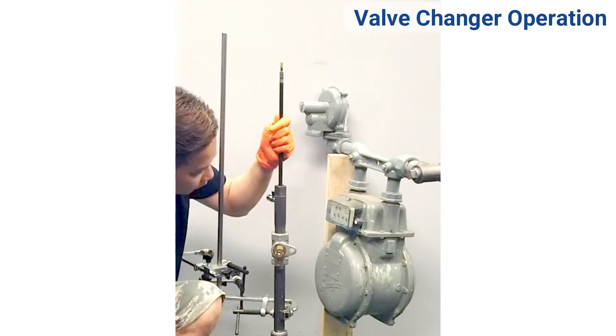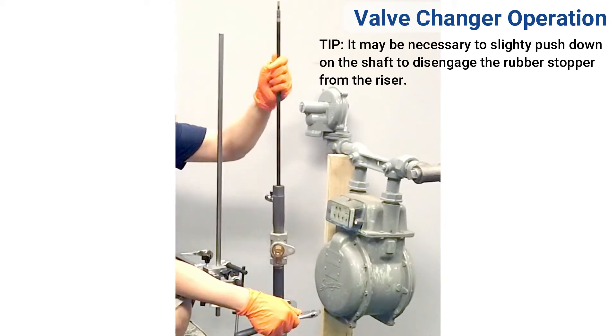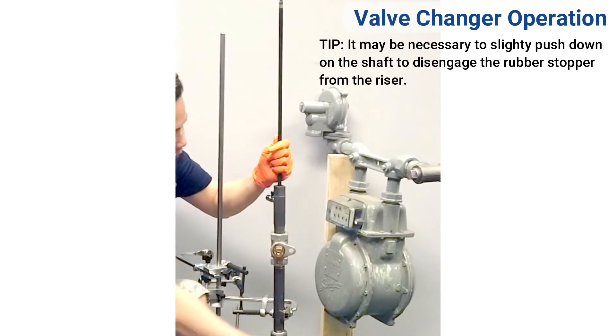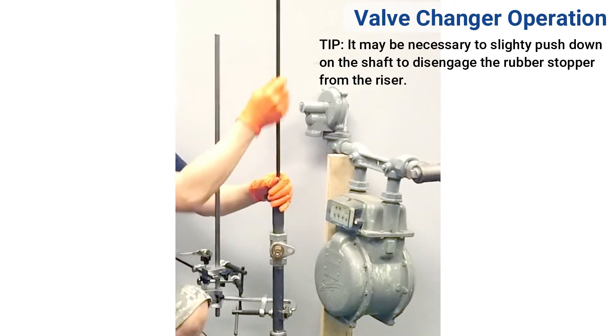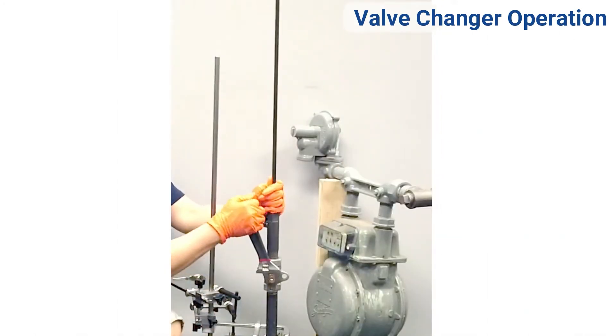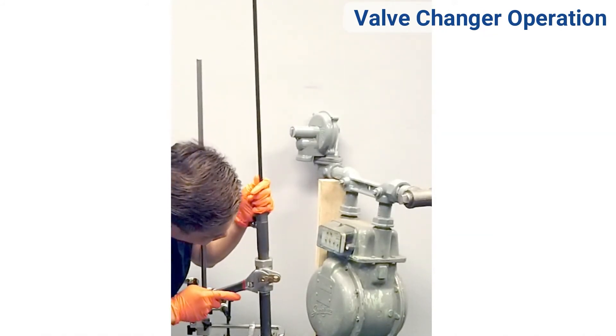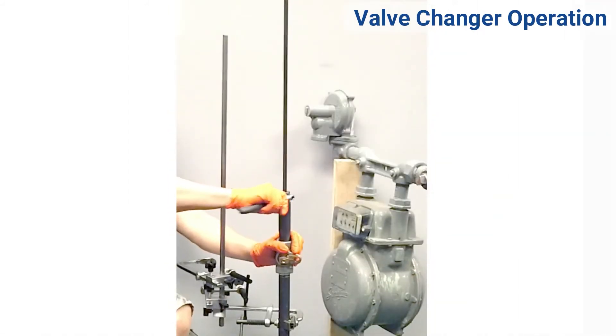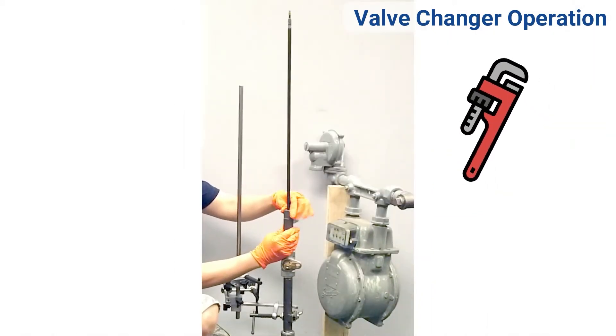Retract the rubber stopper into the stuffing box. Be sure to control the shaft with your hand. Turn the shaft as necessary so the rubber stopper will travel through the rectangular port into the stuffing box. Close the meter valve and remove the stuffing box and safety clamp. The operation is now complete. Leak test and reconnect necessary fittings.